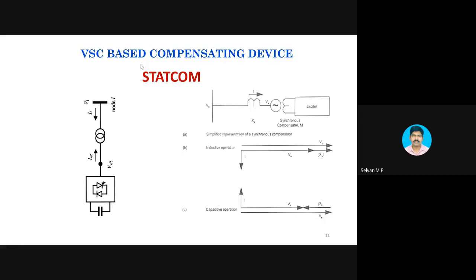You look at the synchronous machine. By adjusting the excitation system, you will be able to control the voltage. By adjusting the speed, you can control the frequency. You can control the real power output. You increase your prime mover, your speed will increase, your real power output will increase. Even there is a coupling: speed increases, your voltage also will increase. Then you have to adjust the excitation system. But in a voltage source converter, when you go for a DQ transformation, the real and reactive power can be controlled independently, as in a DC machine.